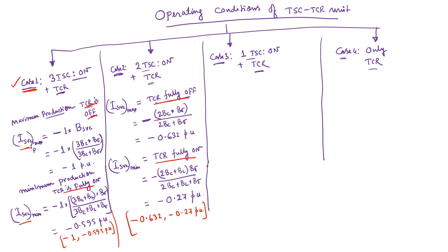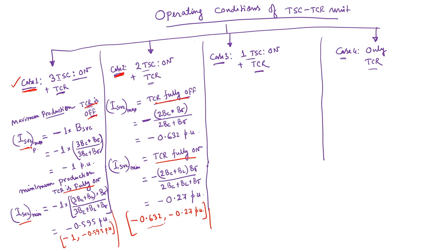So that means in this particular case, when we keep two TSCs turned on and a TCR which can be fully turned on, fully turned off, or partially turned on, we can vary the VAR production from -0.632 per unit to -0.27 per unit. As long as this VAR or this current is coming out negative, that means it is basically producing VAR.